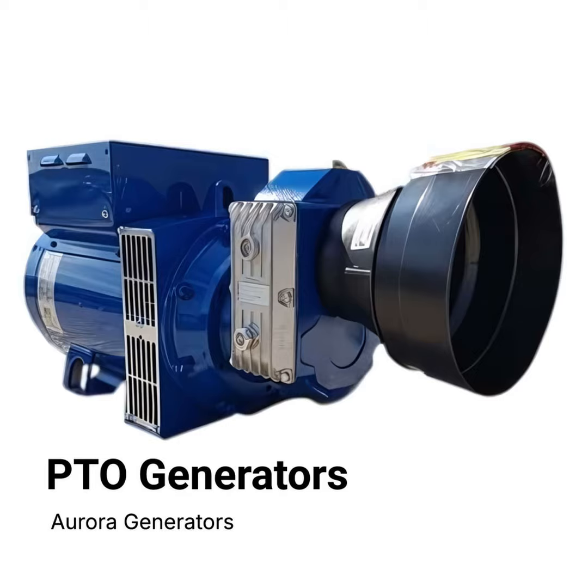Like temperature. Definitely. Most generators are rated for their full output under specific conditions, often something like a maximum ambient temperature of 40 degrees Celsius. So about 104 Fahrenheit. Right. And usually below a certain altitude, maybe 1,000 meters, because the air is thinner higher up and cooling is less effective. So if you're operating in hotter conditions or at high altitude, you might need to derate, reduce the expected output to keep things safe and prevent overheating.